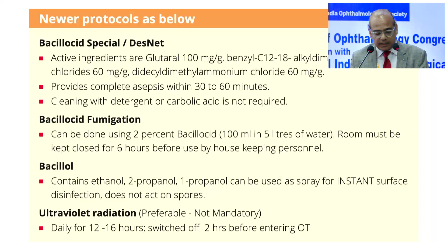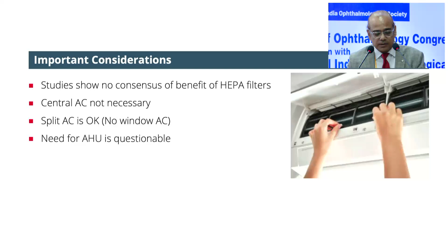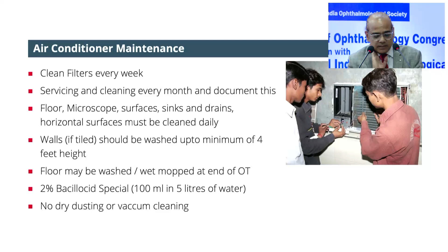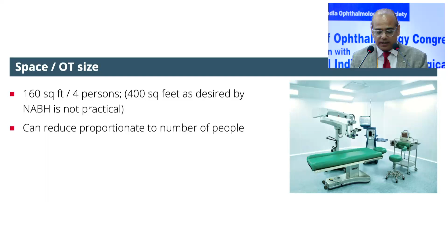What are the important considerations? Studies show no consensus on the benefit of HEPA filters. Central AC is not necessary; split AC is okay. No window AC, it is a big no. The need for AHU is questionable. Regarding air conditioner maintenance, we need to clean filters every week, service and clean every month, and document it. Floor, microscope surface, sinks and drains, and horizontal surfaces must be cleaned daily. Walls, if tiled, should be washed up to a minimum height of 4 feet, and the floor may be washed or wet mopped at the end of the OT, and 2% Bacillocid Special is needed. No dry dusting or vacuum cleaning is to be done. Size: 160 square feet per 4 persons, that is 400 square feet as desired by NABH, is not practical, so we can reduce it in proportion to the number of people entering the OT.